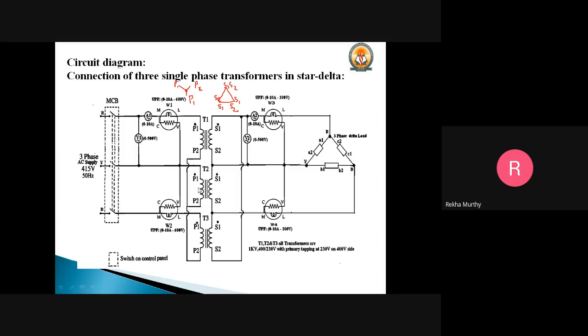So on the board, what you have to prefer is the primary side: 440 will be at the P1 terminal, but you should not take that, you should take 50% of it tapping, so it is 230. So we are preferring 230 here on all three transformers. On the other side, we want 230, so you have to keep it on the 230 side only. Okay, so you have to make that clear while doing the connections.